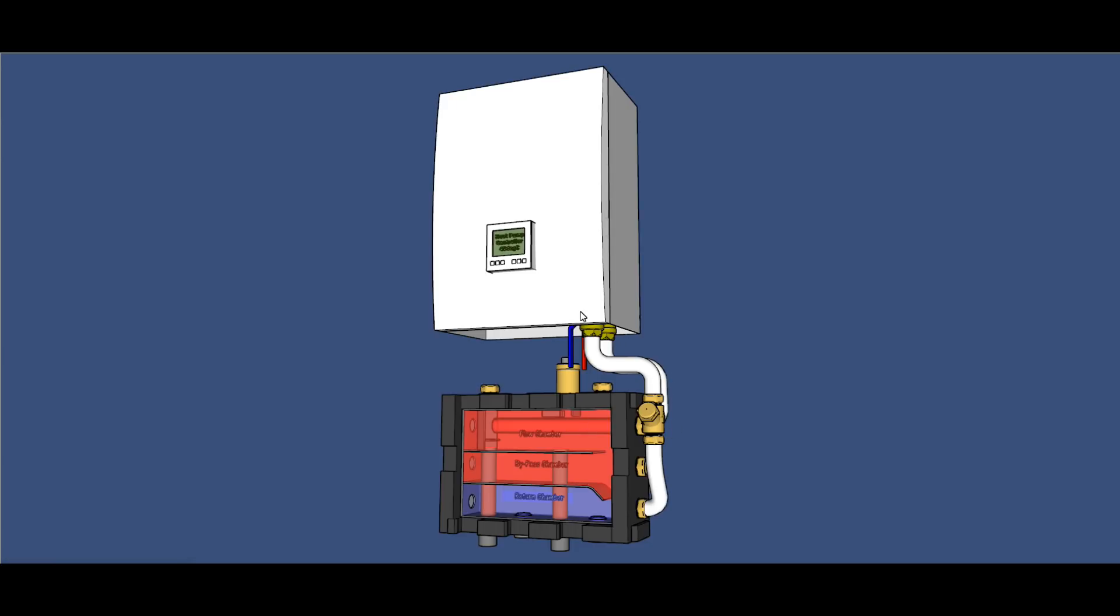The flow comes off the boiler and arrives into the top chamber. The return carries on down. As with a heat pump or any boiler that has small waterways, you'd put a strainer on the return back out of the manifold, catching any dirt that would block any heat exchanger. This is only necessary where the appliance itself requires a strainer, but this is where you would locate it.